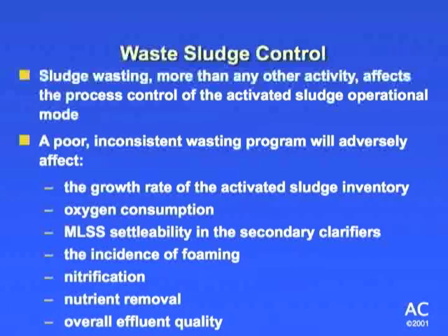For a short period of time, I've seen some plants where, and I worked at this one, it was fun, somebody forgot to stop wasting. Because wasting was basically opening a valve on the RAS line, and we really didn't have a way to monitor it too well. We just did it by hours and assumed that we were doing okay by opening this valve for a certain amount of hours, and somebody just left the valve open and they caught it the next day that they'd overwasted. It was bad.